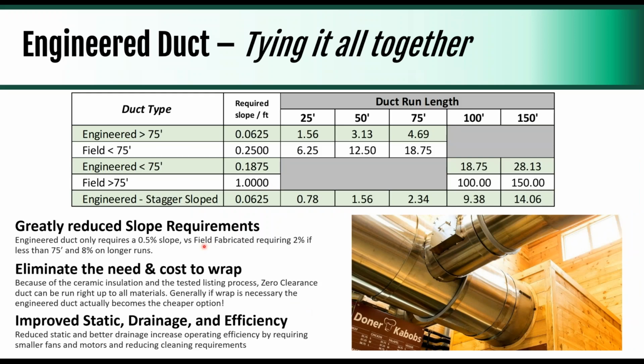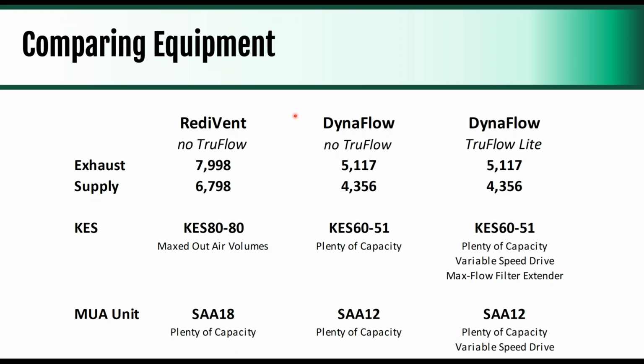Engineered duct also has greatly reduced slope requirements. So rather than the traditional 1/4 of an inch slope for field fabricated duct, you're actually only using a 0.5% slope. So it's a significant difference, especially if you're running over 75 feet, where field fabricated duct needs to have a very significant slope of 1 inch per foot, whereas engineered duct needs to only have 1/16 of an inch per foot. You also eliminate the need and the cost to wrap by using the zero clearance duct. It's also got, because it's round in nature, improved static drainage and efficiency. So in some cases, you're seeing reduced horsepower on the fan or smaller fan sizing because you're using the engineered ductwork.